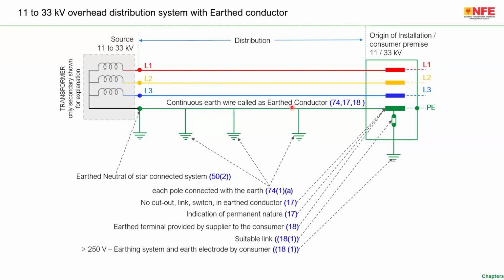Regulation 17, regulation 18. This means if you have an overhead line from the substation to the origin of installation, imagine in a consumer premise you have an 11 kV or 33 kV transformer up to the consumer premise, there must be a continuous earth conductor, which is a requirement of regulation 74, regulation 17 and 18. The earthed neutral of the star connection, any system which you are using, the star point has to be earthed. This is in regulation 50 sub-regulation 2. In the distribution, the earthed conductor also is to be earthed, which is in regulation 74 sub-regulation 1A. No cutout link or switch shall be included in the earthed conductor, regulation 17.